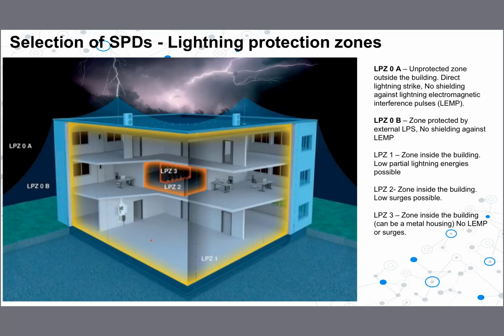The next one, actually this one was already answered in the lecture itself, but the second part I think is important. The question is, Engineer Badam, is it okay to connect SPDs to the common earth bar of a distribution board? I think you explained that in the lecture. Yeah. Here our challenge, as I explained, is to reduce the cable length. So definitely we have to connect it to the distribution board earth, because otherwise, if you run the earth wire, the cable directly coming out from the SPD to an external earth terminal or something, then the cable loop length will be high. So then it exceeds the 50 centimeter limit.